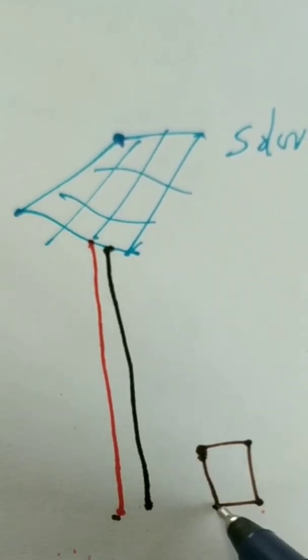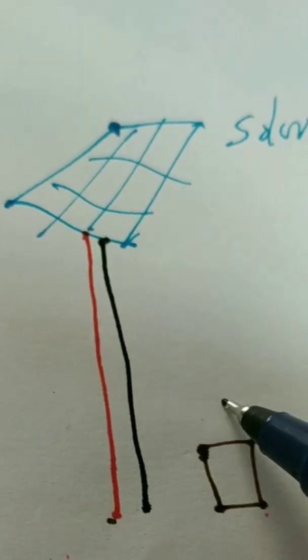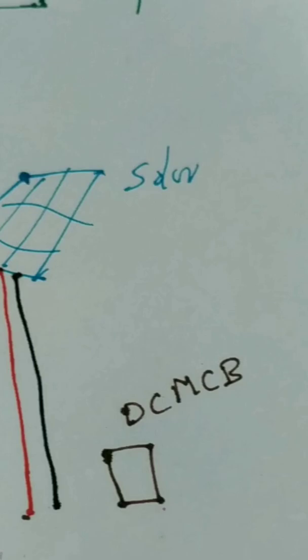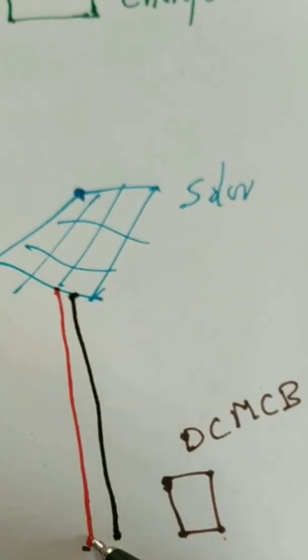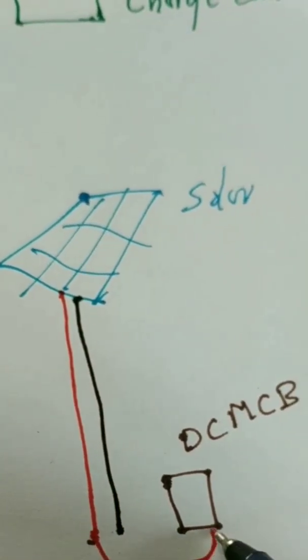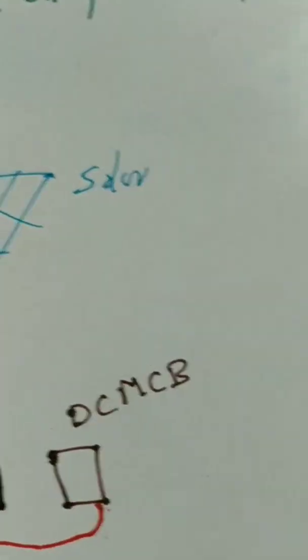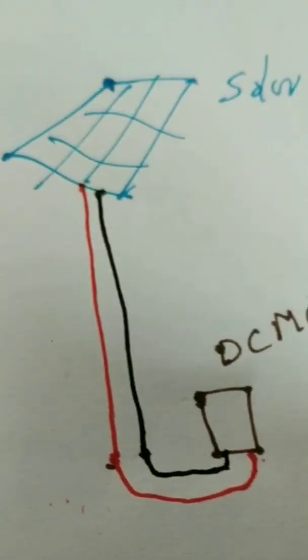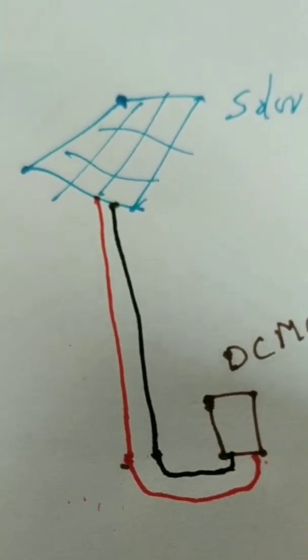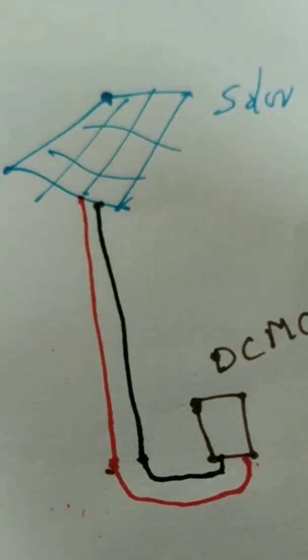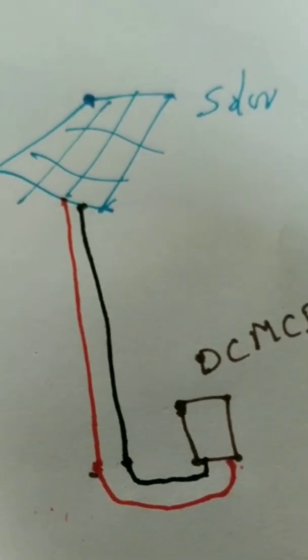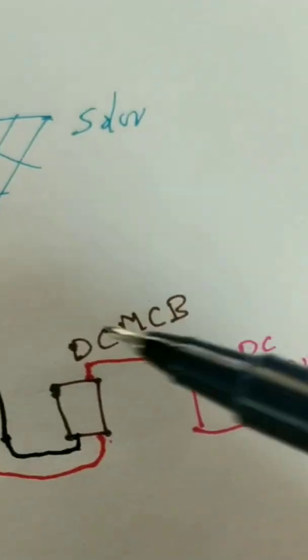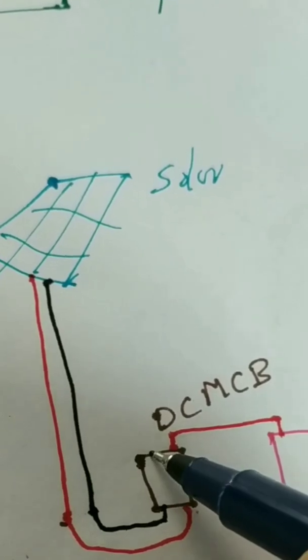I have installed one MCB also. So first, the solar panel positive and negative will be connected to a DC MCB, and from the DC MCB positive and negative will be connected to a surge protection device which is in parallel. And from SPD, positive and negative will go to the inverter, solar inverter, or charge controller.